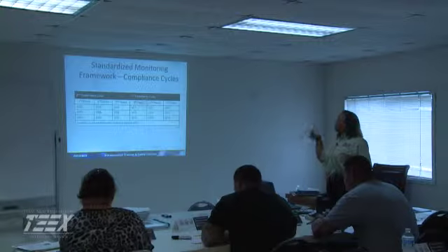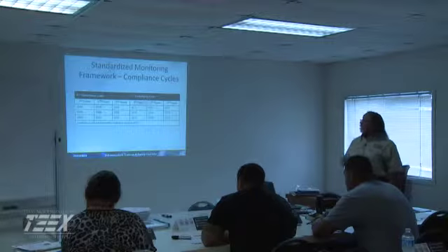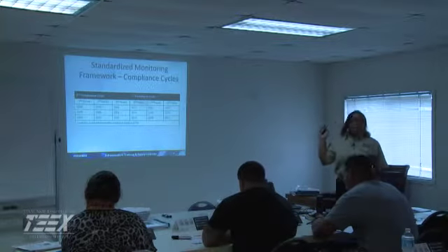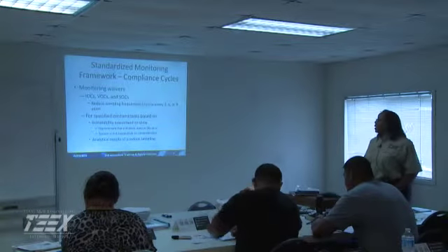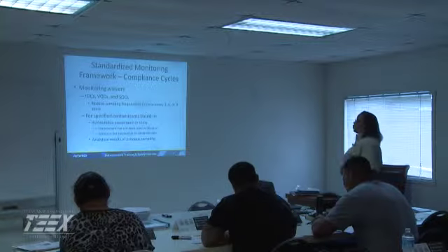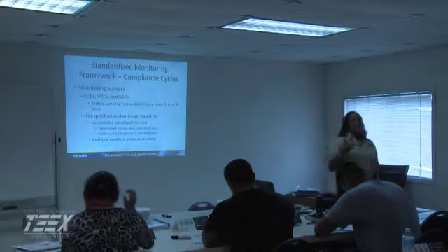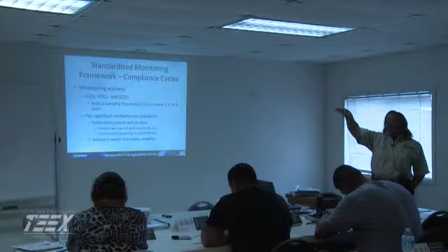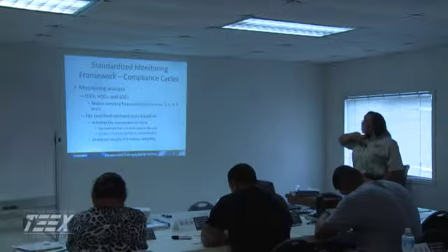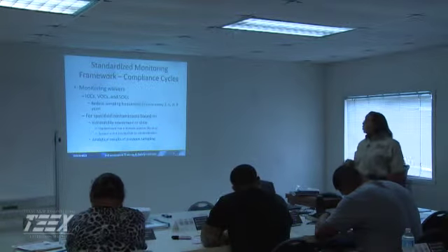All right, and this right here you do have in your book. Again, it just gives you the compliance cycle for the first, second, third period. That reference or framework started with the second period because that's where we were. Okay, with your waivers. Again, waivers and exemptions simply reduce the sampling frequency, but in order to reduce the sampling frequency, you have to show you've been a stellar participant and you've had no hits whatsoever. And with that, your reductions can be every 3 years, 6 years, or 9 years. And that's where you want to be.